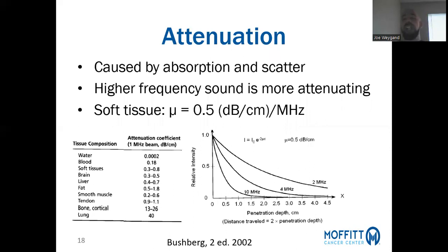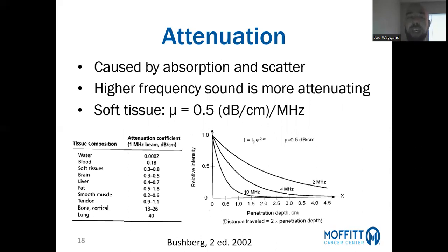Attenuation is caused by absorption and scatter. Higher frequency sound is more attenuating — a 2 MHz beam penetrates quite deeply into a patient, while a 10 MHz beam may only penetrate about 2 centimeters. The attenuation coefficient for soft tissue is approximately 0.5 dB per centimeter per megahertz.